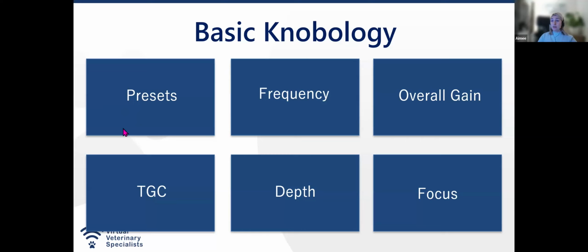So the first one is your preset. So this is when you click on abdomen or small dog abdomen, large dog abdomen, cat abdomen. This will then give you a baseline for that scan, okay? So the manufacturers have put into that machine what they think you need for that medium dog abdomen. That preset should usually adjust these other 5 for you. Well, these other 4, it won't affect the TGC unless you've got a brand new machine. This is a manual function, okay? So your preset will set all these for you at what it thinks you need.